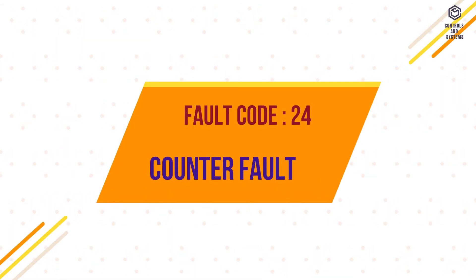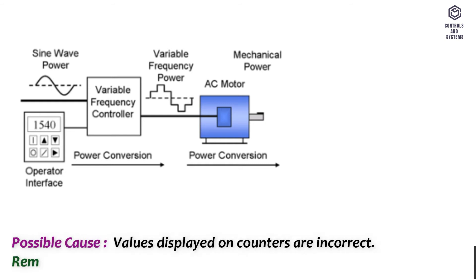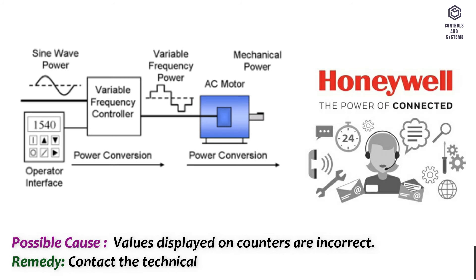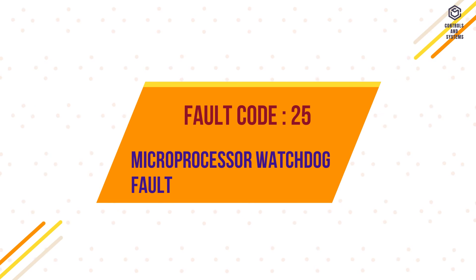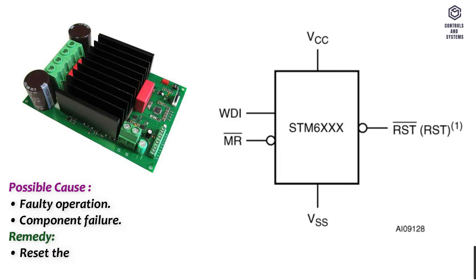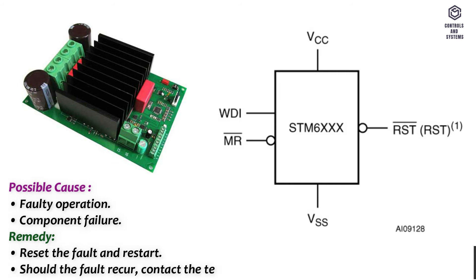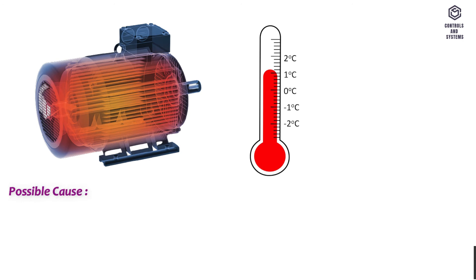Fault code 24 – Counter fault. Possible cause: values displayed on counters are incorrect. Remedy: contact technical support. Fault code 25 – Microprocessor watchdog fault. Possible cause: faulty operation or component failure. Remedy: reset the fault and restart; should the fault recur, contact technical support.